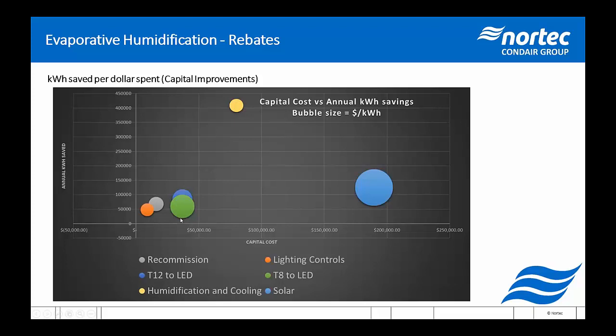If you have T8 light bulbs and drop down to LED light bulbs, it's a smaller bubble. If you're looking from T12 to LED light bulbs, it's an even smaller bubble. If you just recommission the building, that's one of the most cost-efficient ways of saving yourself energy per year. And just putting in lighting controls so that the building isn't lit up year-round 24/7 is another very inexpensive way to save some money. Interestingly, switching out your electric humidification to an evaporative humidification system is more expensive than switching out your lighting, and it's more expensive than doing a recommissioning, but the size of the bubble is quite small, and that's a very positive thing. That means the number of dollars we spend to save thousands of kilowatt hours per year is very small comparatively.